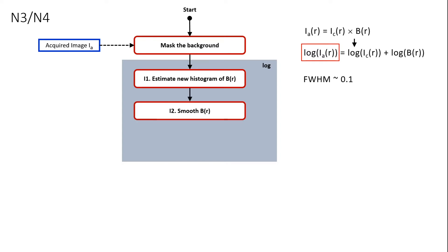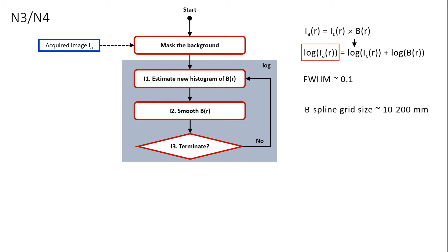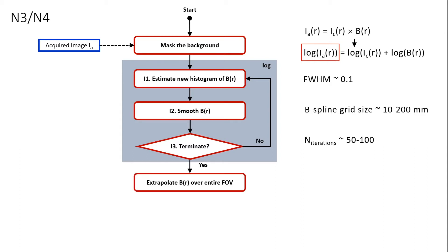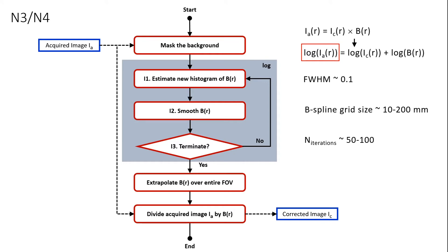In step 2, the new estimate of the bias field is smoothed by fitting it with a three-dimensional B-spline field with a specified grid. The size of the grid controls the degree of smoothing. This grid size is typically about 200 mm for images acquired with a body coil and smaller for images acquired with localized surface coils. In step 3, the termination criterion is tested against a specified threshold. In practice, the algorithm stops after a fixed number of iterations specified by the user. Once the iterations are completed, the bias field is extrapolated over the entire field of view. Finally, the original image is divided by the bias field to obtain the corrected image.